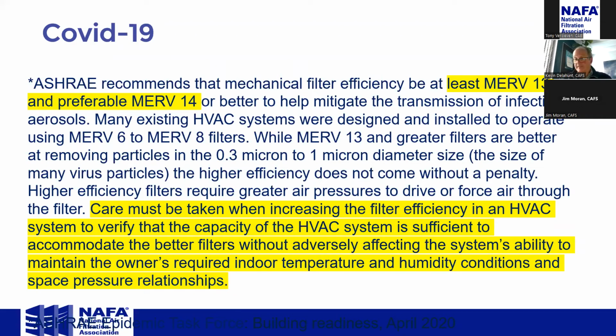Ventilation is every bit as important as the filtration during the pandemic. There were even lots of comments at the first about putting a HEPA filter in, which would dramatically reduce the ventilation into a space. So the balance between airflow and filtration has to be taken into consideration, and sometimes it's very difficult in older units to do that. So, okay.